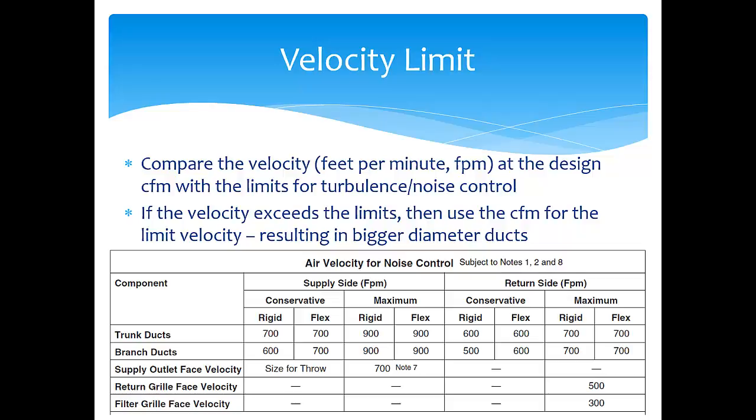If the velocity given by the slide rule for a particular combination of friction rate and room CFM exceeds the limits set by Manual D, then you use the room CFM combined with the maximum allowable velocity as your sizing metrics. The slide rule table also gives you the velocity limits for trunk and branch ducts, whether made of rigid or flexible material. That rounds out the basics of sizing the air distribution system.